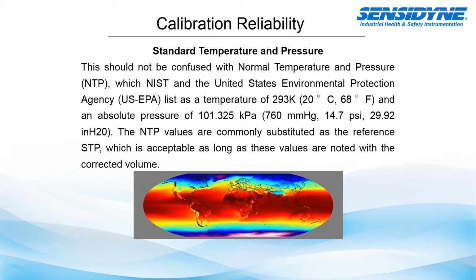Again, when you're measuring standard temperature and pressure, make sure that you're not confusing it with normal temperature and pressure. Again, in the United States, NIST and the EPA list normal temperature and pressure as 293 Kelvin, which is really measured at 20 degrees C or 68 degrees Fahrenheit, and an absolute pressure of 101.325 kilopascal, which is 760 millimeters of mercury, or about 14.7 psi, or if you're measuring in inches of water, it would be 29.92, just under 30 inches of water. The NTP values are commonly substituted for STP, which is acceptable.